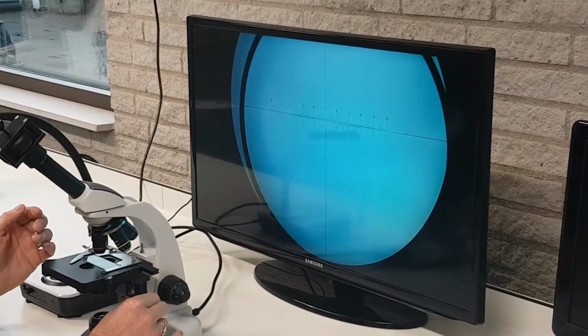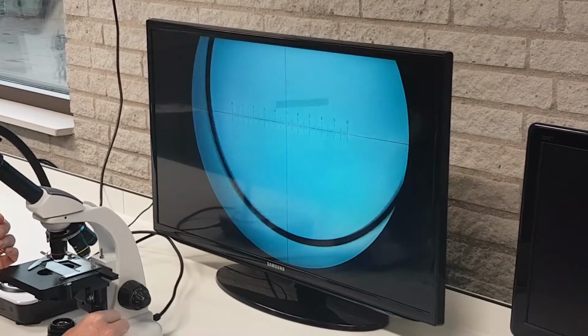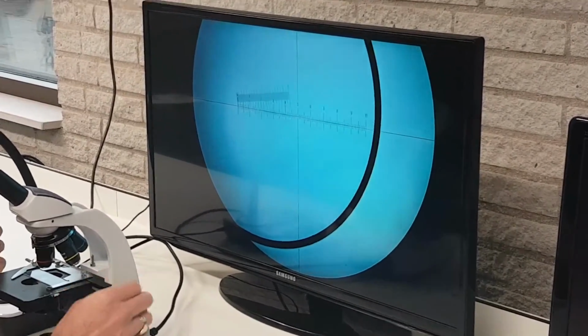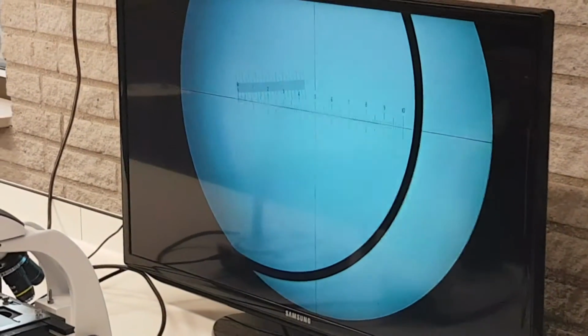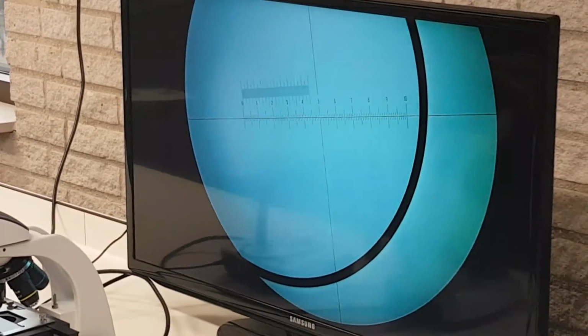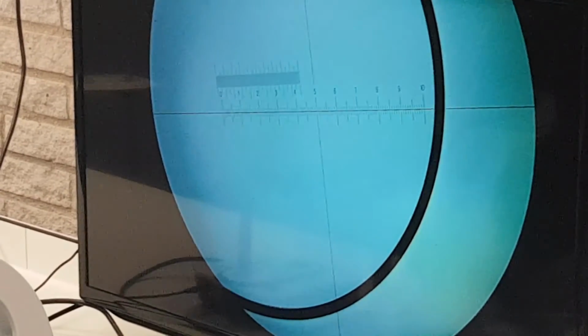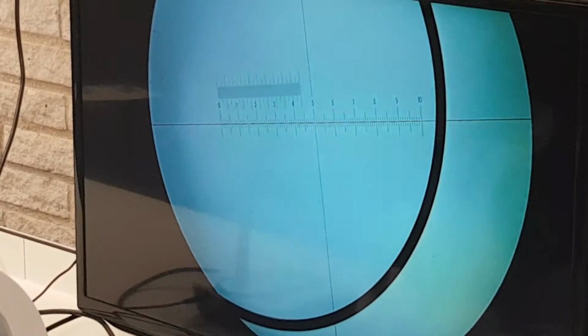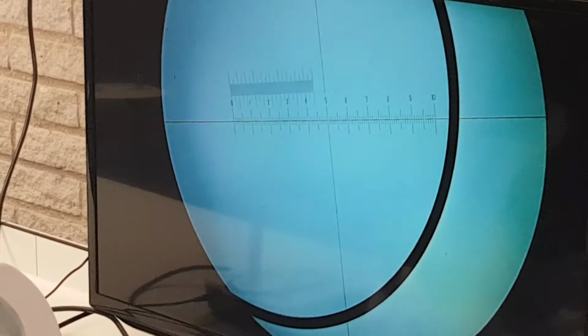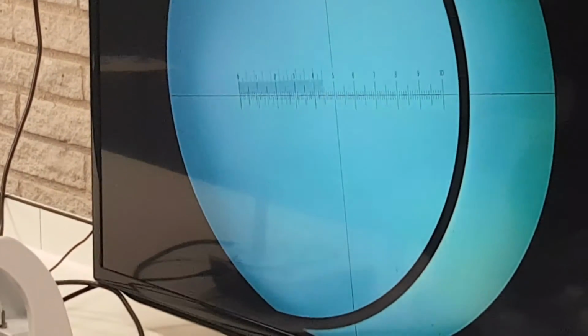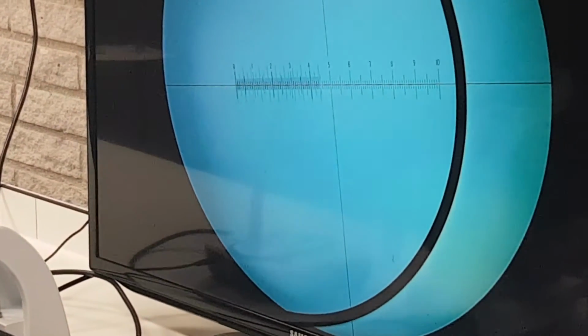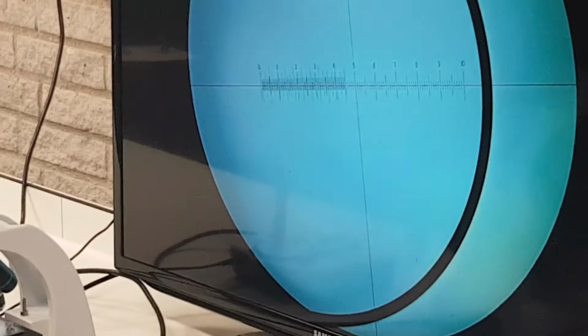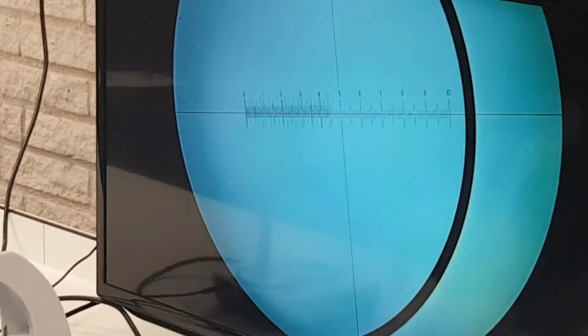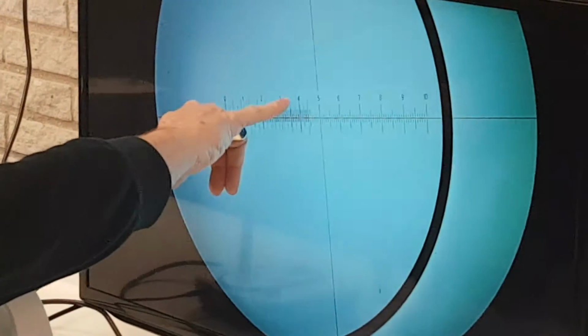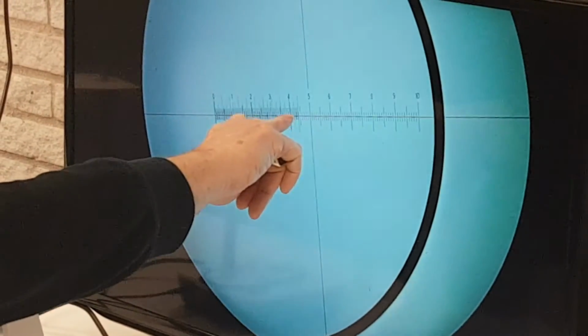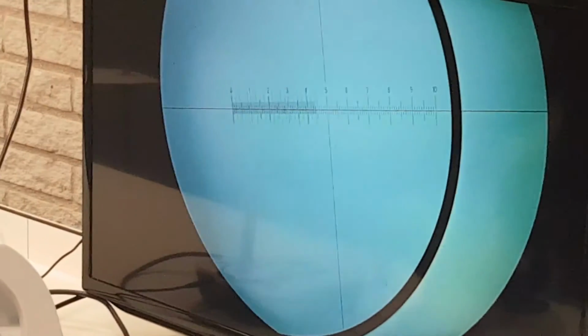What we're going to do now, we put exactly the stage micrometer and the eyepiece reticule in line with each other. I can turn this a bit like this. Move with the mechanical stage, the stage micrometer exactly on top of the scales of the eyepiece reticule. Make sure you line them properly. And if I read now, then I can see that 1 millimeter equalizes 44 stripes in the eyepiece reticule.